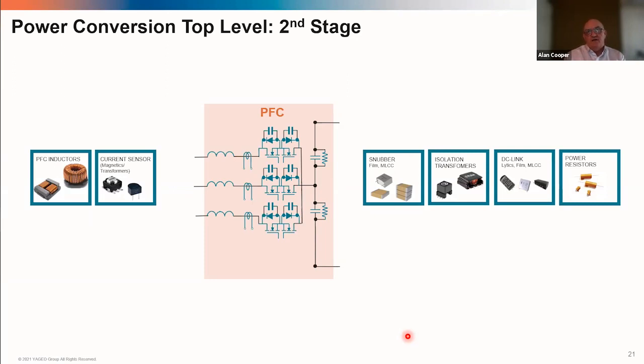The current sensors are there to measure the current so you can control the current going into the two capacitors in the DC link. The switches are there to chop that up in terms of how you want to fill the capacitors. The capacitors again will need protection with snubbers. We'll talk about that in a minute, and also the isolation transformers and the DC link.